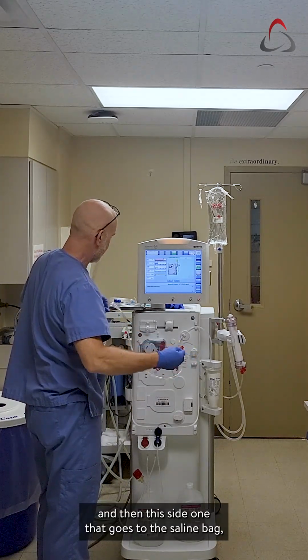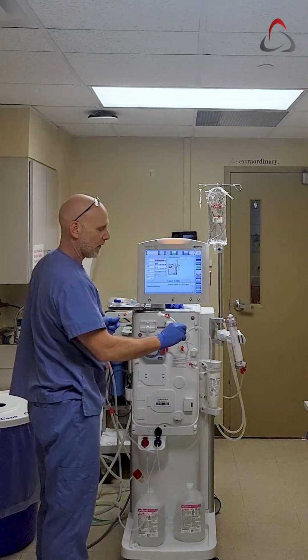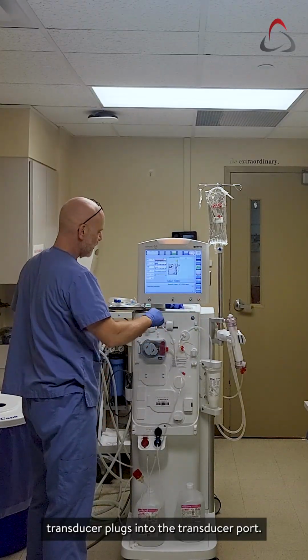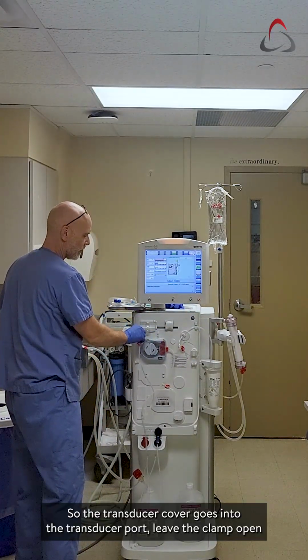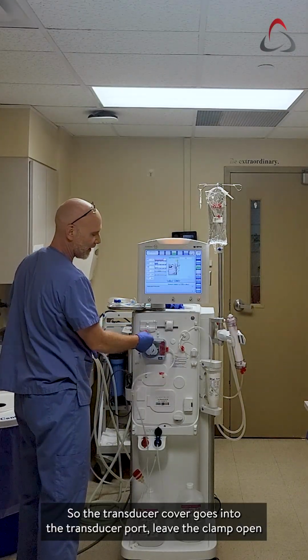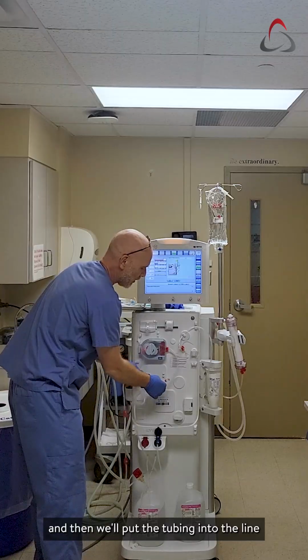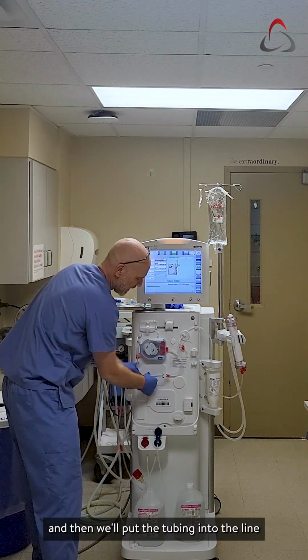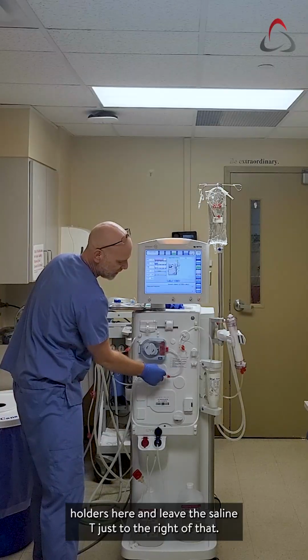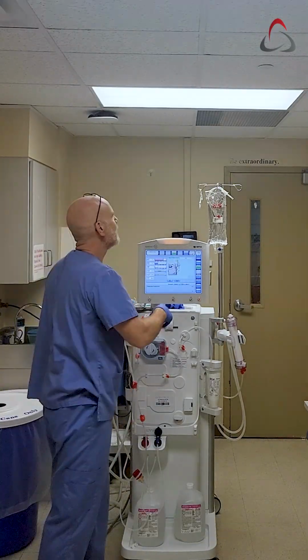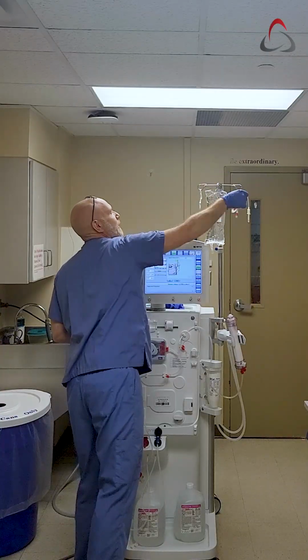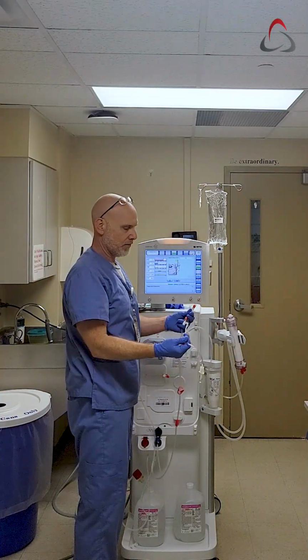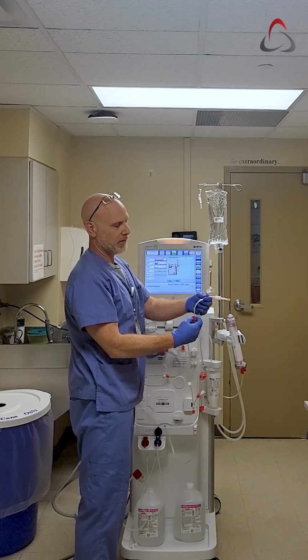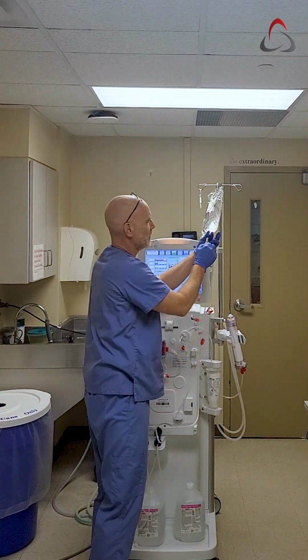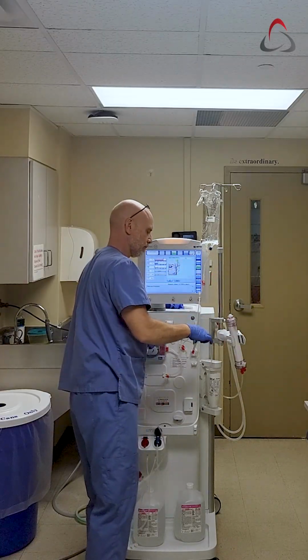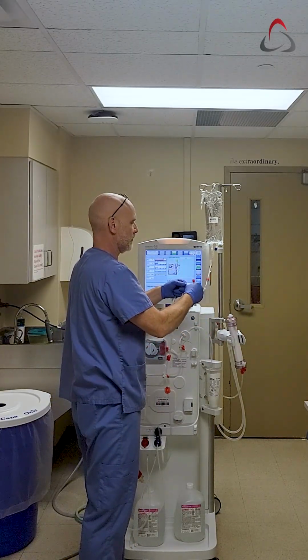And then this side, the one that goes to the saline bag, you just have your transducer that plugs into the transducer port. So the transducer cover goes into the transducer port, leave the clamp open, and then we'll put the tubing into the line holders here and leave the saline tee just to the right of that. That's where it's most accessible. And then we'll plug in our saline. So clamp your saline line, spike your bag, connect the two lines together.